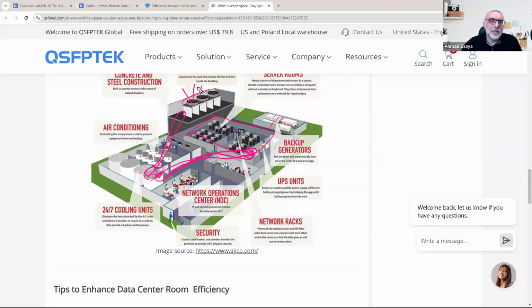This external unit will dissipate the heat. So somehow it is all about heat exchange. We want to take the heat from here to there. We have a unit here to absorb the heat and send cold air inside this room. The heat absorbed from here is transferred through one loop to the chillers. The chillers take the heat and send it to another loop. These loops are totally independent for different reasons; we don't want to have just one loop. Then they take the heat and send it to another unit, which is responsible for dissipating the heat into the outside ambient environment. This way we take the heat from here to there.